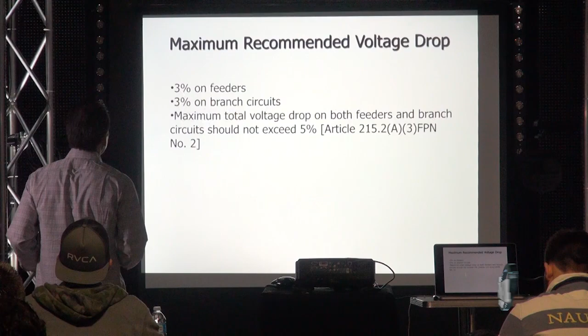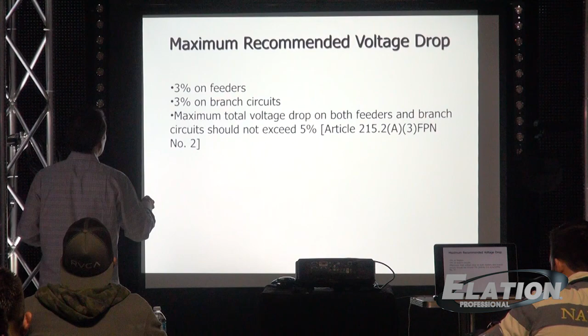According to code, the maximum recommended voltage drop, and I say recommended because it used to say the maximum allowable voltage drop, and they changed the wording. I don't know why that is. But nevertheless, you really should not have more than 3% voltage drop, and that's 3% on the branch circuits or 3% on the feeder cables, no more than a total of 5% voltage drop from the supply to the load.